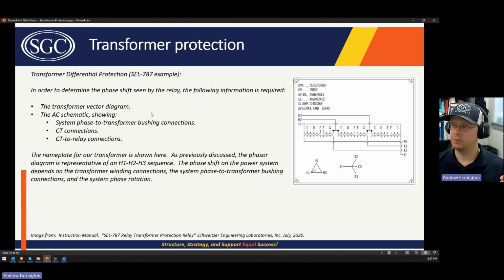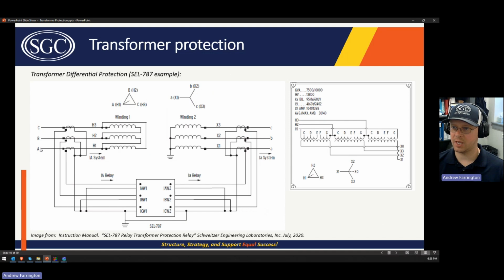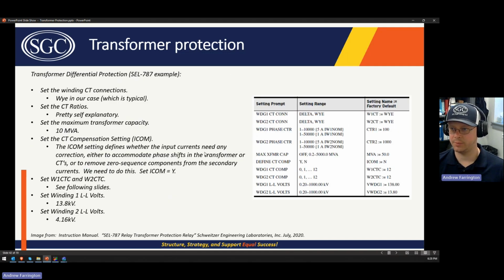So what information, I got ahead of myself again. What information do we need in order to set that compensation setting? We need the transformer vector diagram, which in this case is a DY1, as we just went over. You also need the AC schematic, which shows the system phase to transformer bushing connections. So here we have A is connected to H1, B is connected to H2, C is connected to H3. Pretty simple, but you may not have these phase to bushing connections, right? You could have a different rotation. So that would play into whether or not this is actually a DY1 transformer when connected to the grid, or if it's DY11. Depends on that sequence. Here it's ABC, so it's going to match the nameplate.